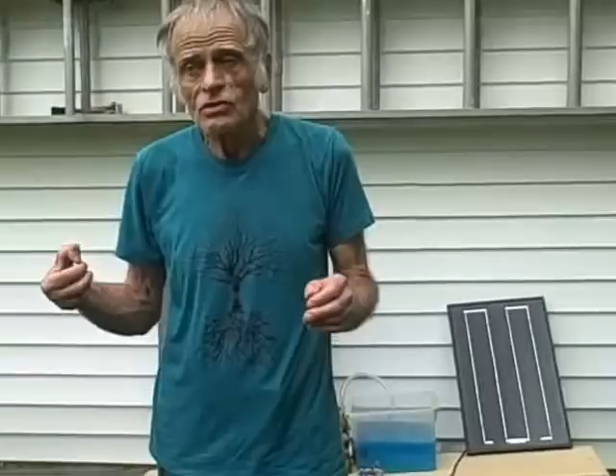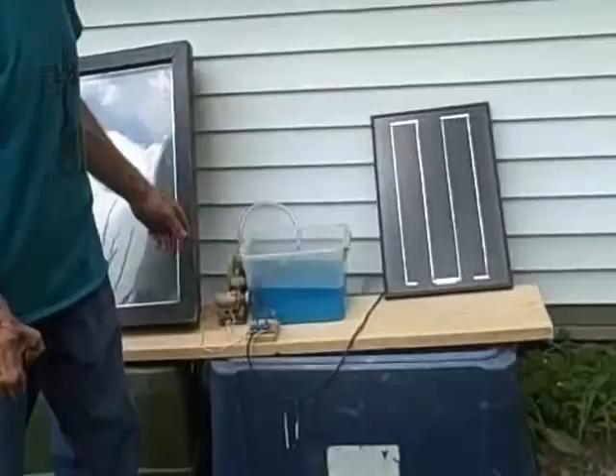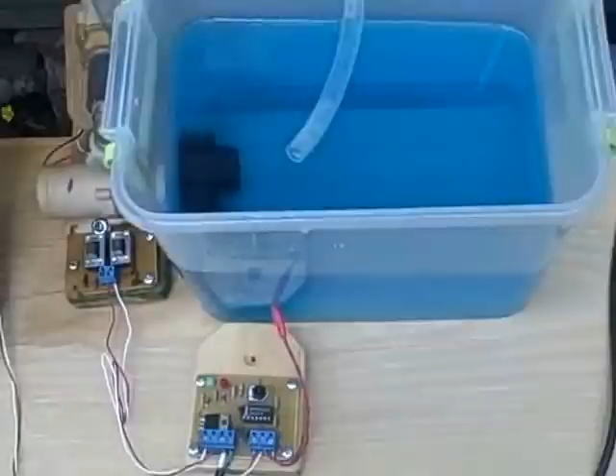So what can we do to increase our efficiency of collection rather than connecting our photovoltaic panel directly to our pump? What we can do is connect it to a differential controller like this. This is called a PV controller because it works directly with a PV panel. It has to go through this first, so it's not only does it need sufficient power from the sun, it also needs heat.